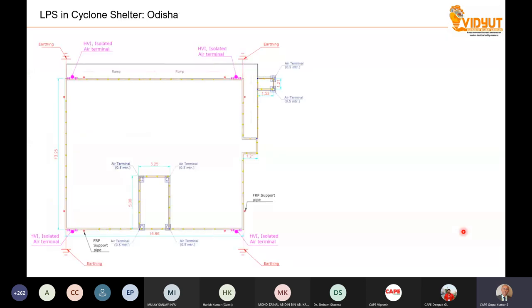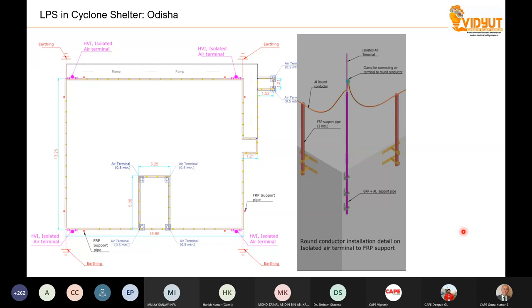Another case, cyclone shelter in Orissa. This is the tender document. A cyclone shelter, I have a picture I will show you. It's a normal RCC building. Probably the height of the building is 7 to 8 meters or maybe 10 meters, a normal RCC building. You have to understand that people inside an RCC structure are protected. People inside a substantial building are protected, provided the metallic plumbing system and the metallic power lines are connected to the equipotential bonding system. So lightning protection, air termination, down conductor and earthing is required for this particular building, not to protect the people, it is to protect the building itself.